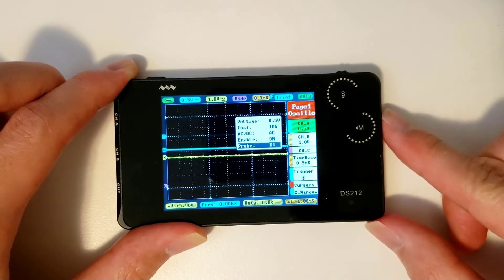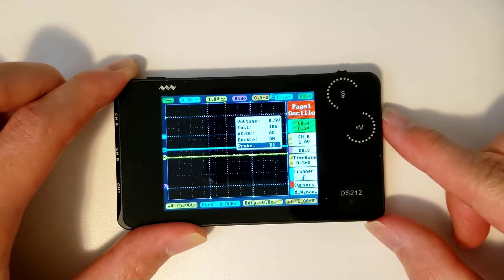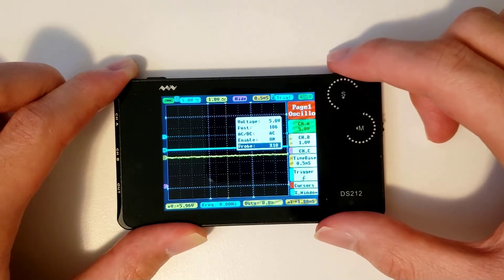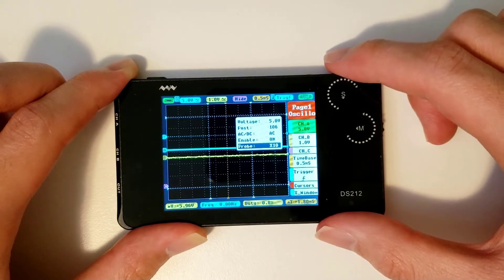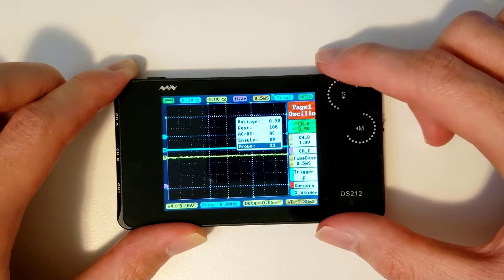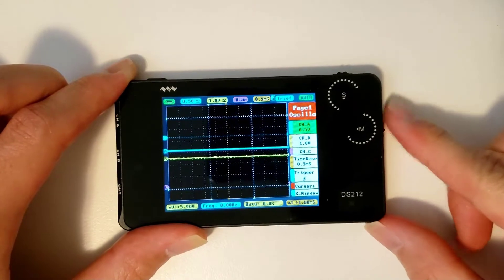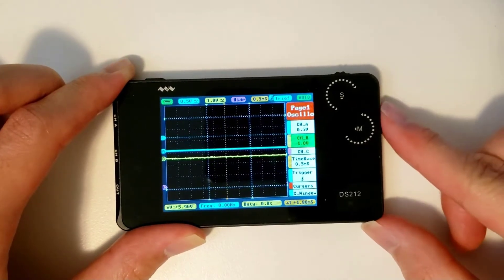The probe option asks you whether you're using a 1x or a 10x probe. The probe that shipped with the scope is a 1x probe, so keep this parameter at 1x.